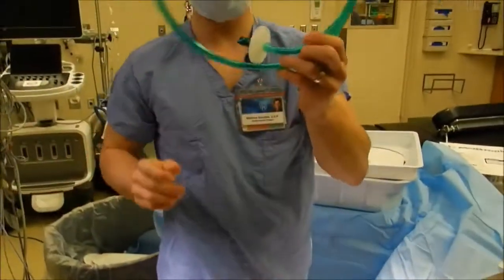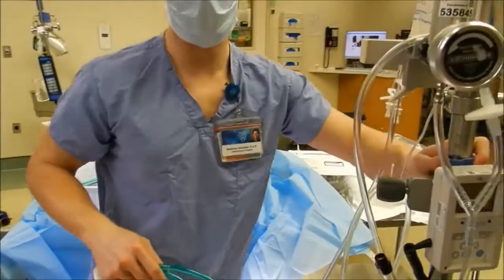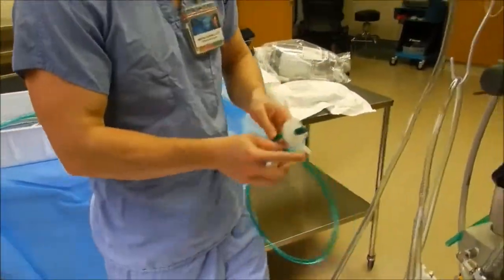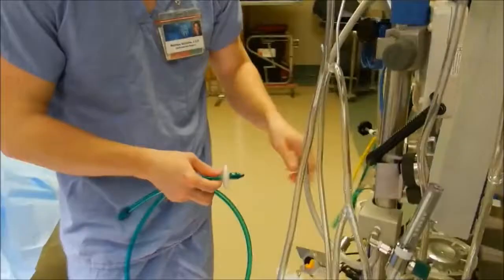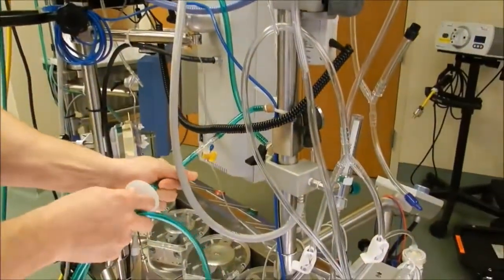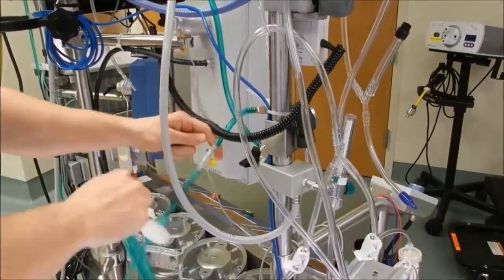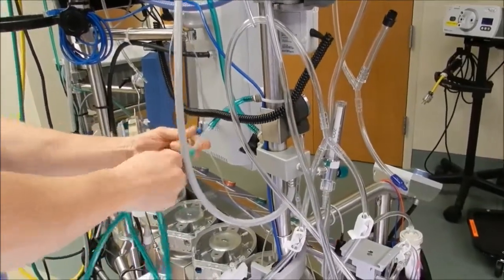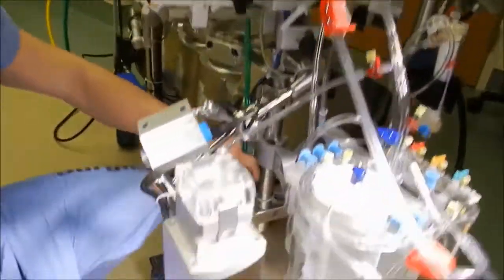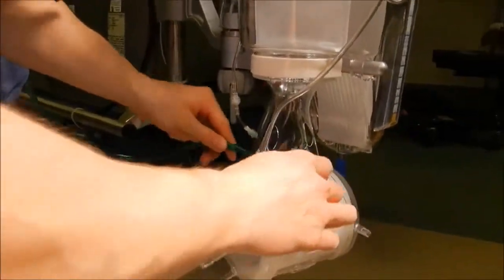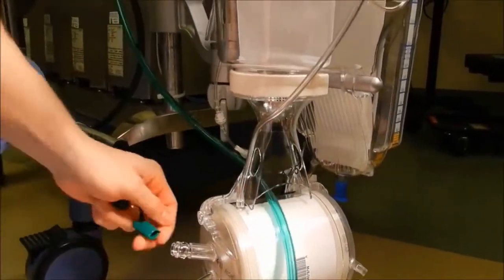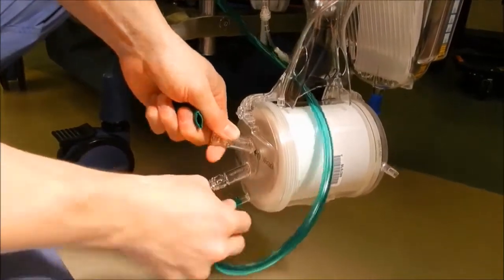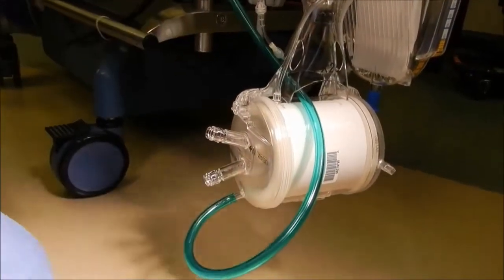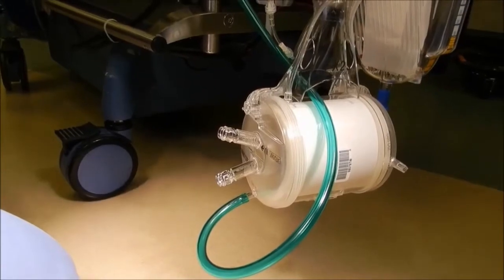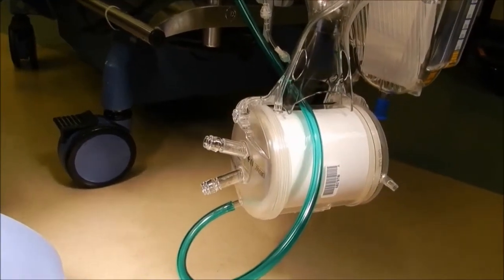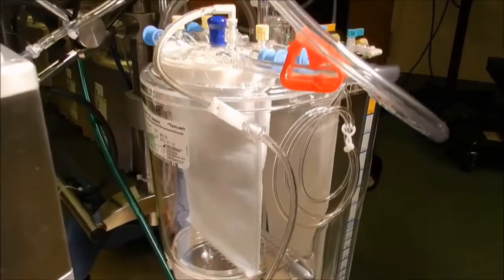One of our most important lines, the oxygen or gas connection to the oxygenator. So we'll go ahead and hook that up. It's the only piece of green tubing we have on here, so safety. And I just interlace that through. That way if it gets pulled, it shouldn't come out of either connection.